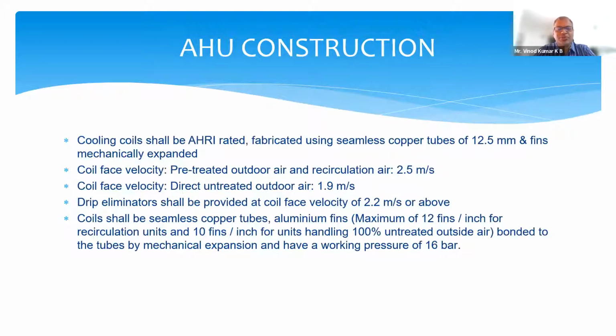Now, imagine you're taking the air through the coil. The air has got a lot of humidity in it. Now, the moment the air touches the coil, which is cold, the water vapor in the air starts condensing and starts dripping as water droplets into the drain pan. As such, what happens? The water gets carried forward and it goes into the theater, spoils your HEPA filters and makes a messy situation with fungus growth in the HEPA filters or water dripping inside the grill. So you have to make sure that the selection is of the right velocity.